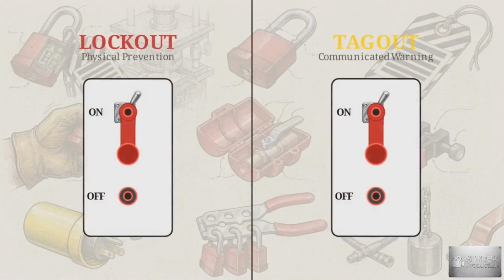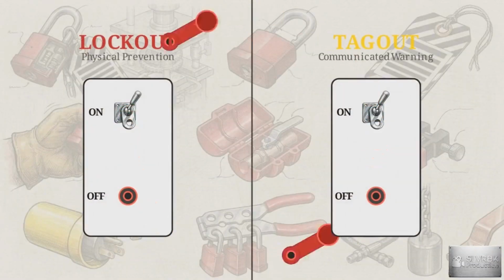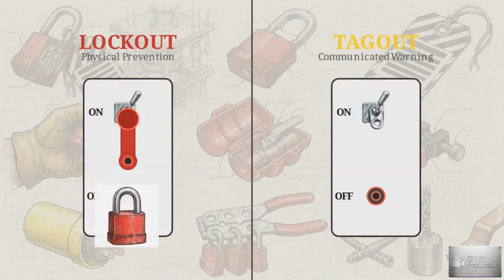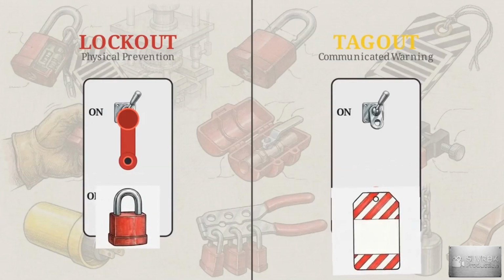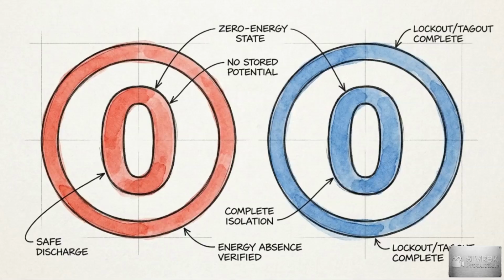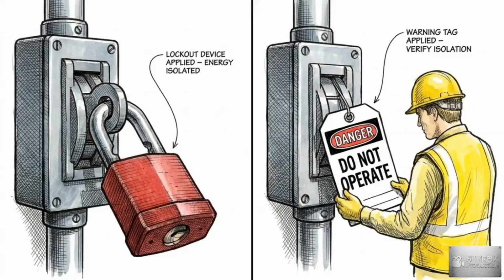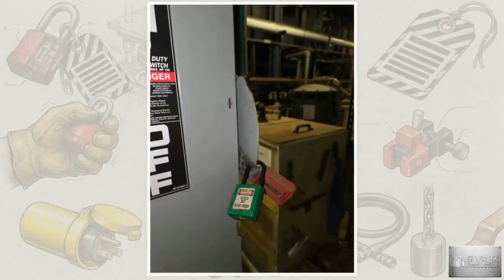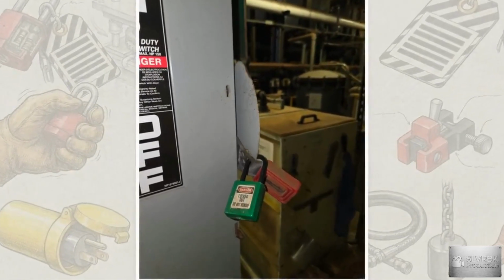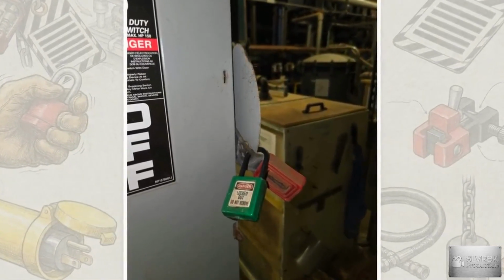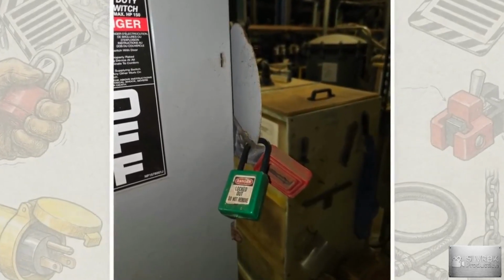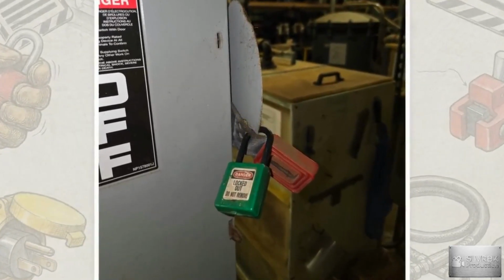To ensure those isolating devices stay in the off position while a worker is inside the machine, OSHA recognizes two distinct systems: lockout and tagout. While both aim for a zero-energy state, their functional differences determine how much the safety of the work environment relies on physical hardware versus human compliance. Lockout relies on physics. It is defined strictly as the application of a positive physical restraint that holds an isolating device in the safe position.